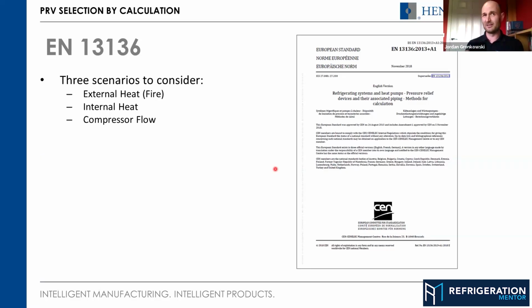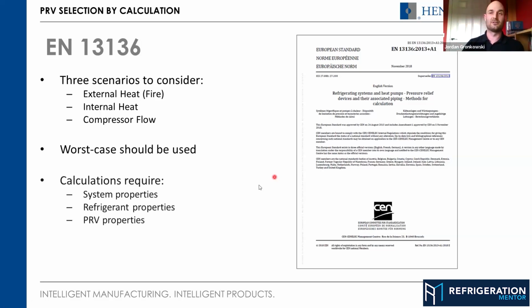So again, typically for transcritical CO2 systems, we sometimes see valves located on the discharge line, and they will be sized to cope with the flow rate of the compressor. So if there's some blockage further down the system, the valve will open and allow the total flow rate of the compressor to be discharged. And the standard then says that you should consider as many of these as are applicable, and you should obviously use the worst case for what valve to pick. So there's some calculations involved, which we'll dive into in a sec.